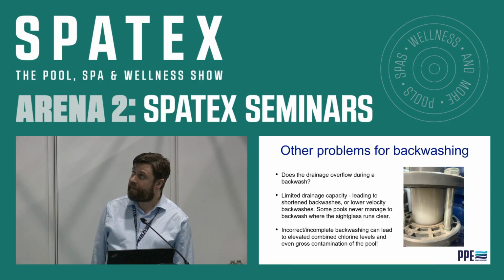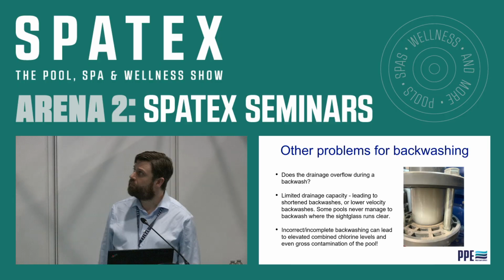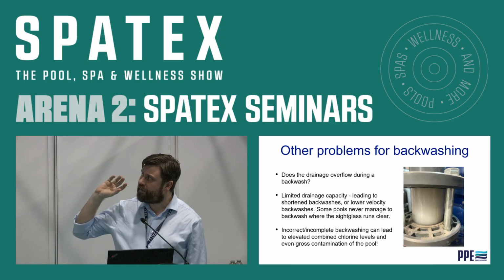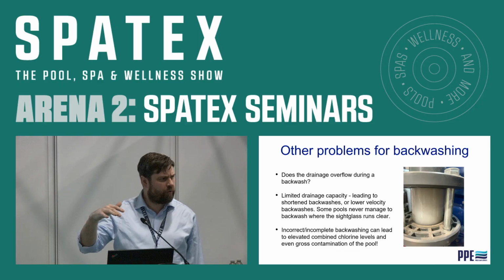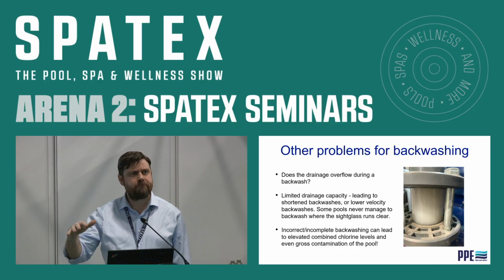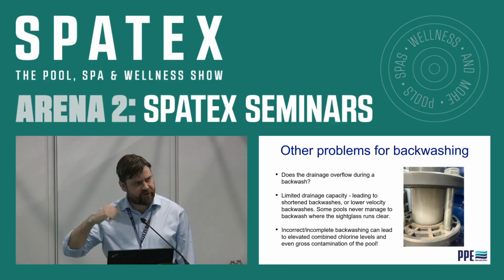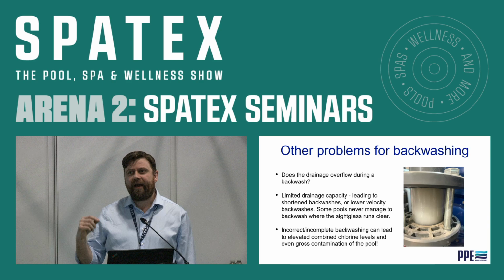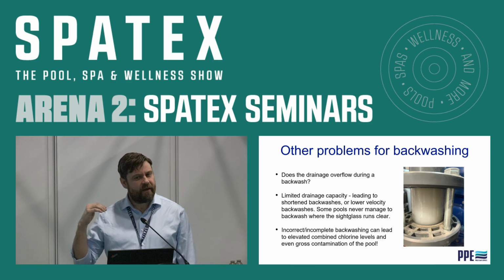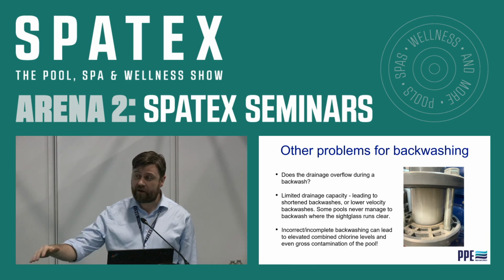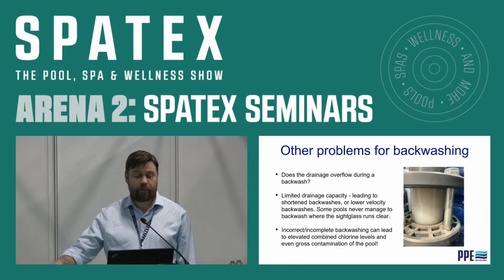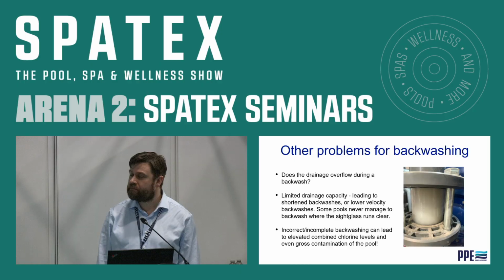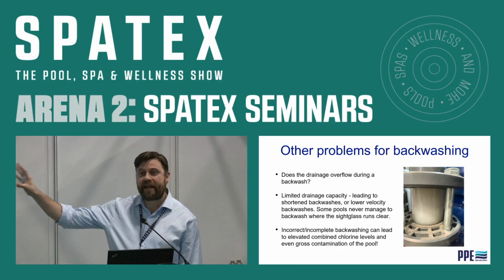Other issues that we can have with backwashing, I think this follows on quite nicely from Lynn, who was speaking just before me, is just ask yourself a question. When you actually do a backwash, and we've got quite a few pool operators here, a few, so you manage to backwash, sight glass always goes clear? Yeah, happy days. Have you been to sites where they backwash, or you might have spoken to some of those staff, and they can't backwash for the full amount of time? They flood the drains. And they never actually manage to clear the sight glass.